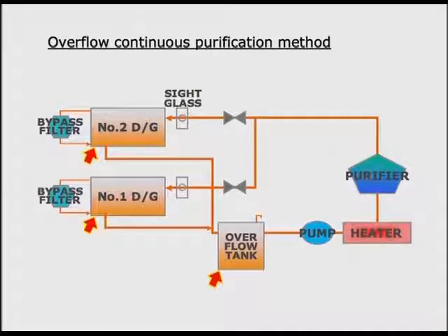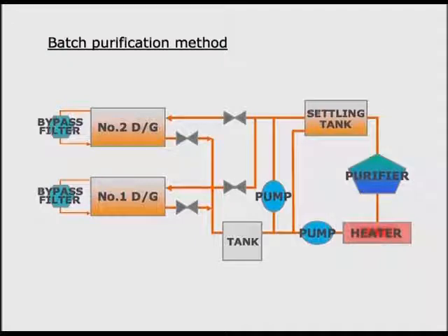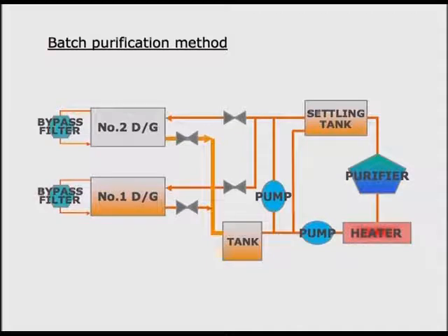For batch cleaning treatment, the lube oil is regularly replaced by cleaned lube oil. Therefore, you need to determine the replacement interval by watching the dirt level of the lube oil in the sump tank. For example, transfer the lube oil of number two diesel engine generator to the tank.